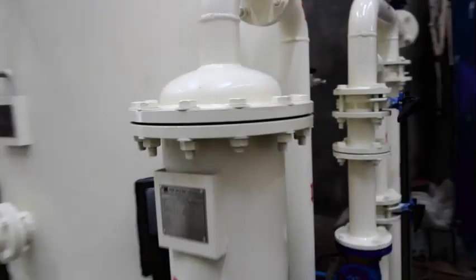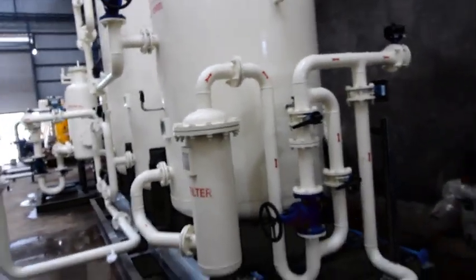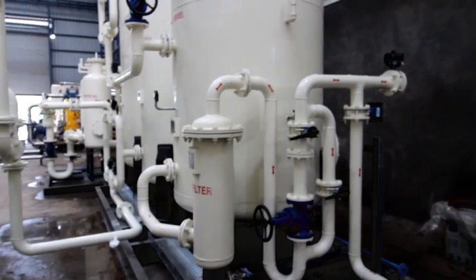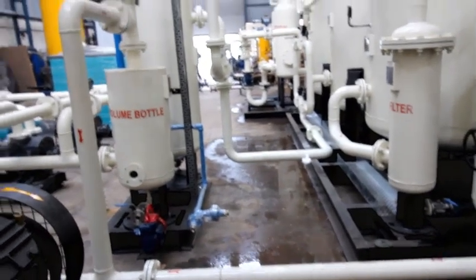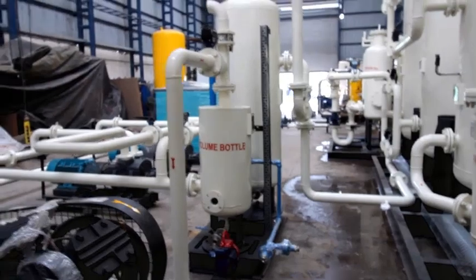After analysis, if the purity of the gas is achieved in the surge vessel it proceeds forward; otherwise, the impure gas is sent back to the suction of the blower for recirculation through the VPSA system until it achieves the purity set in the analyzer.